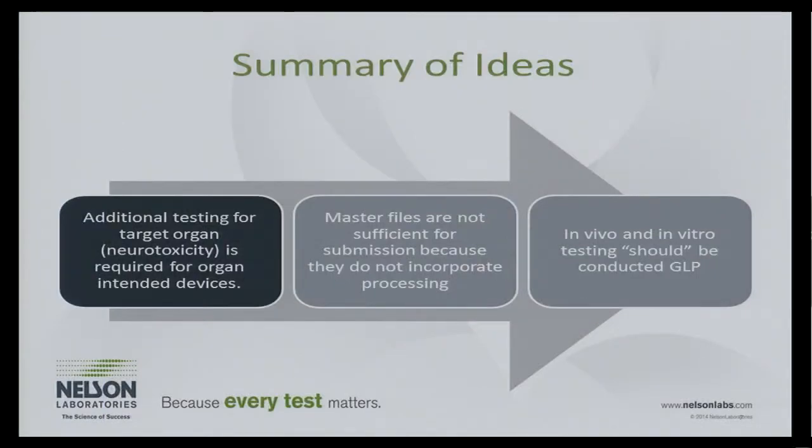What did the master file have done to that material? Was it sterilized or was it a non-sterile product? There are some questions that we have to answer to be able to assess the biocompatibility, even if it has a master file. The testing should be conducted GLP.